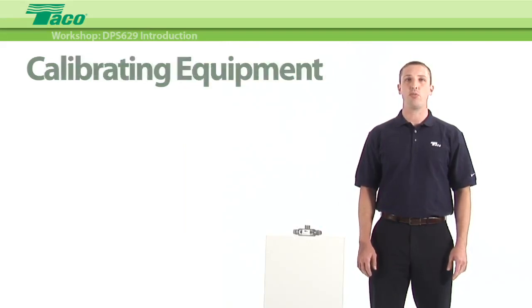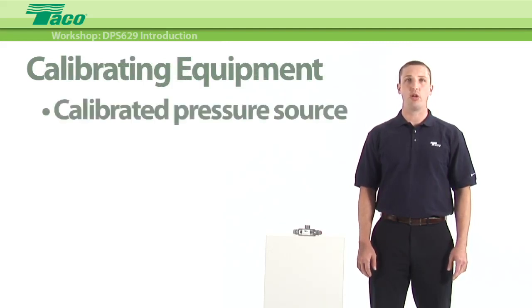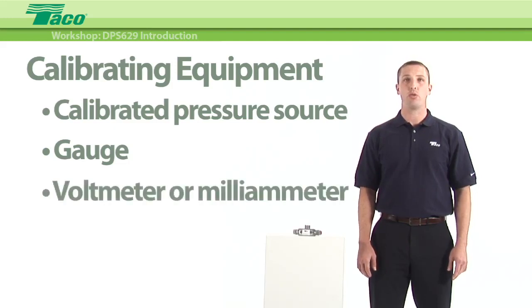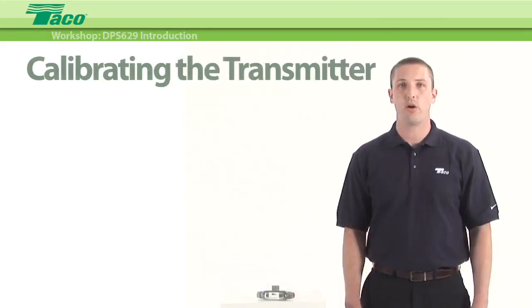To calibrate the transmitter, you'll need 3 pieces of equipment. First, you'll need a calibrated pressure source capable of generating a stable pressure value for the maximum range of the unit under test. You'll need a gauge capable of validating the calibration pressure. You'll also need a voltmeter or milliamp meter to calibrate the output. The transmitter is calibrated using the following procedure.